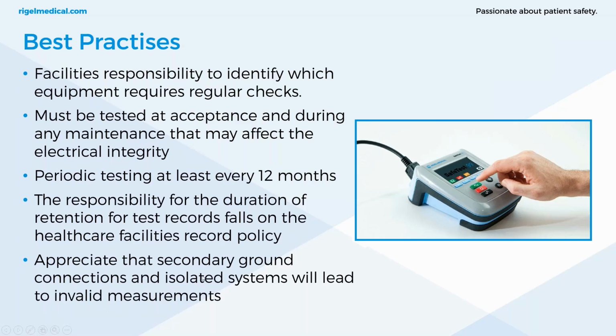You must ensure you appreciate these two factors here. Again, we've got the option on the Safe Test and the Rigel 288 where those issues, if they do come up, if you're on an isolated system or if there is a secondary ground, then the Safe Test is going to highlight that, as is the 288. So our products will have that feature.